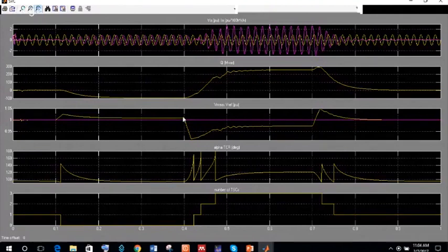Then at this instant, the voltage of the programmable voltage source is reduced. Since voltage is reduced, it must be boosted. So capacitor banks should be switched on. So how many capacitor banks are required? They are taken into the circuit one by one. So first, second, and third. With these capacitor banks, the reactive power that is supplied to the grid has increased. So this is shown by this. Again, voltage is increased.